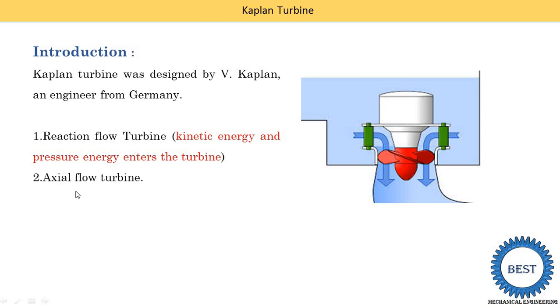Second point: according to the direction of water supply — that means in which direction of the runner water is supplied. This red part is known as a hub, and this is the axis — the vertical axis of the shaft. Parallel to the axis of the shaft, water is supplied; that is known as the axial direction. When deciding the direction, we consider the direction at which water is supplied to the runner. Here it is radial direction entering the casing, but on the runner it is supplied in axial direction, so it is considered an axial flow turbine.